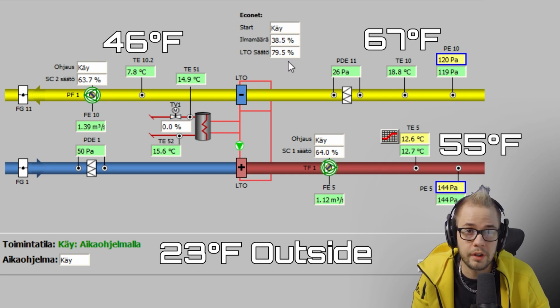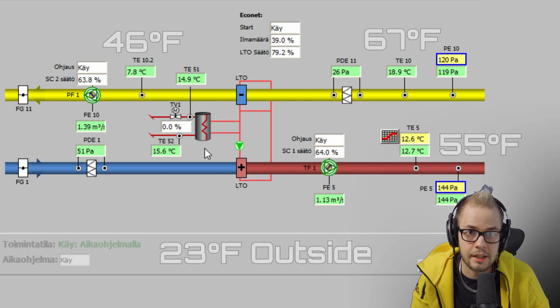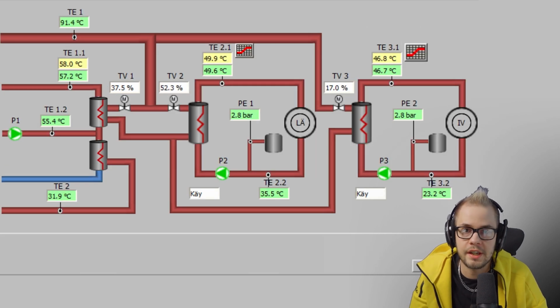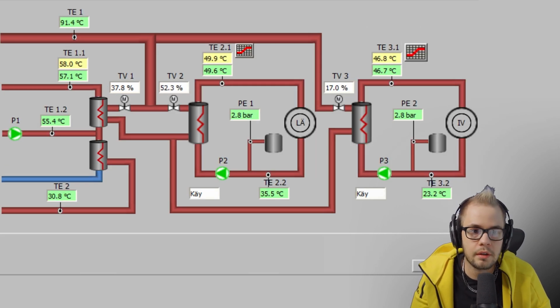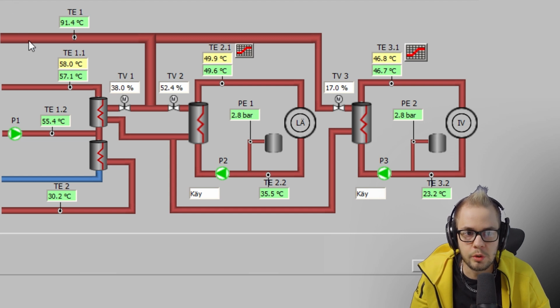If it were colder outside, the heat recovery would ramp up to 100%, plus the valve here would open, so the heat exchanger would receive some energy from the district heating. And here we have the same from the downstairs computer. We have the thick tube on the top, which is the district heating hotline, which is apparently 91.4 degrees right now. It goes to the small heat exchanger for the air heating loop.